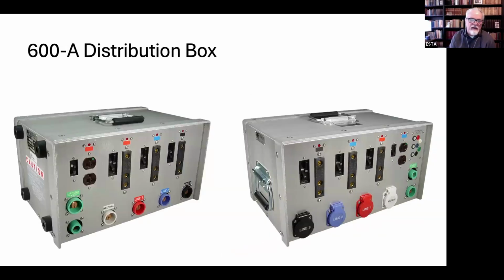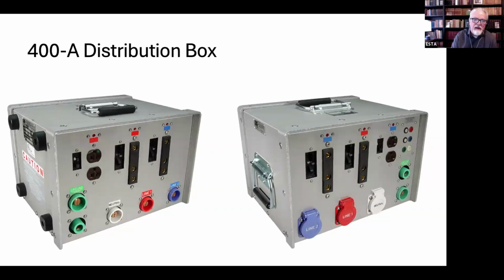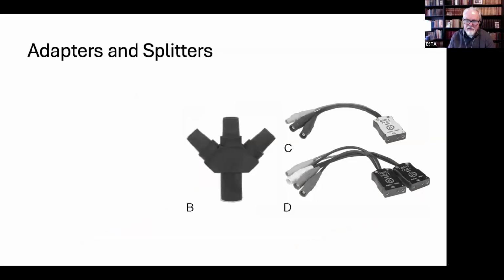All right, so there are a variety of boxes. This is a 600 amp box, so it's just half the size. It still has 5 wires, but not half as many outlets on each one. This is a 400 amp box, which only uses 2 of the phases. So you could have a 3-phase system and just use 2 of them on this box, or you could have what's called a split phase system, which is another rabbit hole that I won't go into unless someone asks me to. But we might talk about it a little bit in another slide or 2.